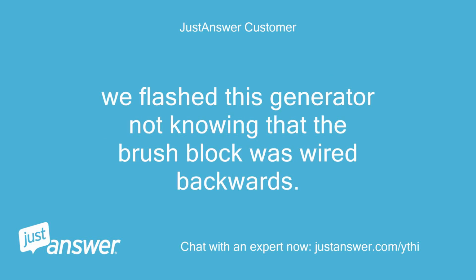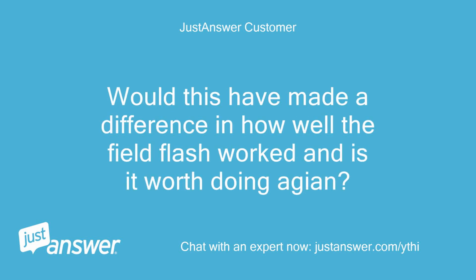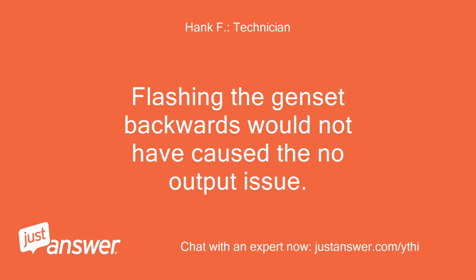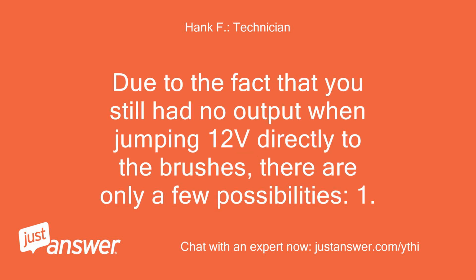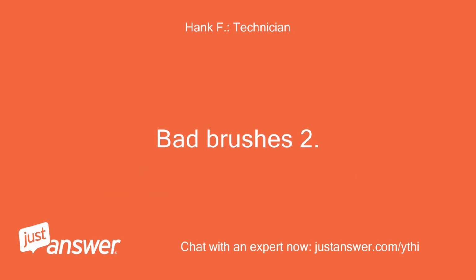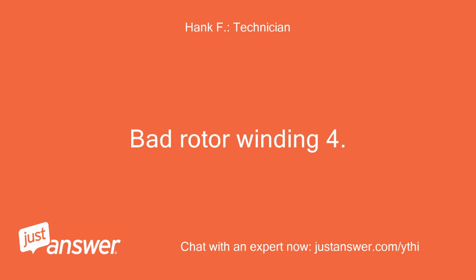We flashed this generator not knowing that the brush block was wired backwards. Would this have made a difference in how well the field flash worked, and is it worth doing again? Flashing the genset backwards would not have caused the no output issue. Due to the fact that you still had no output when jumping 12 volts directly to the brushes, there are only a few possibilities. 1. Bad brushes. 2. Bad slip rings. 3. Bad rotor winding.